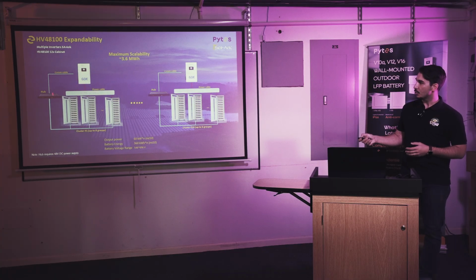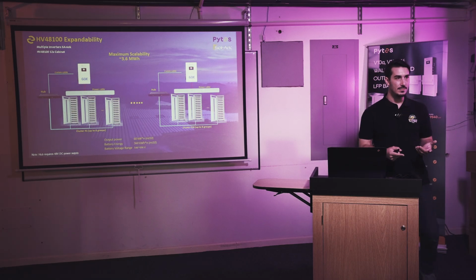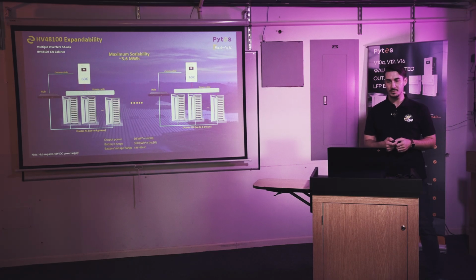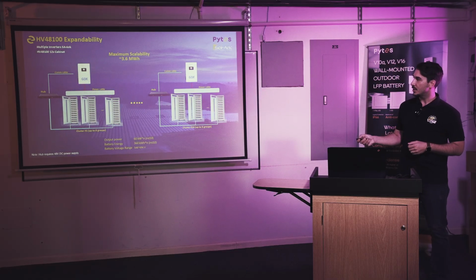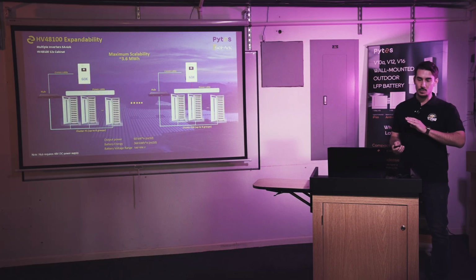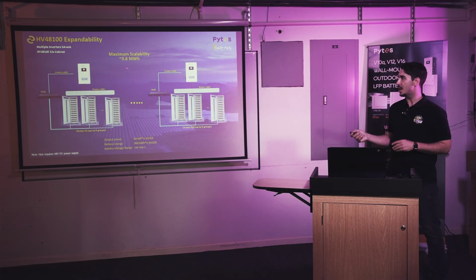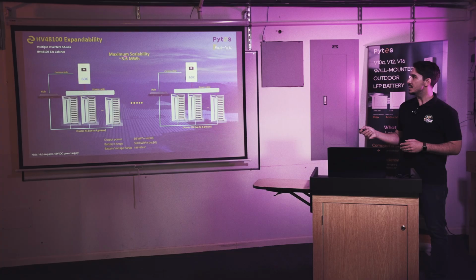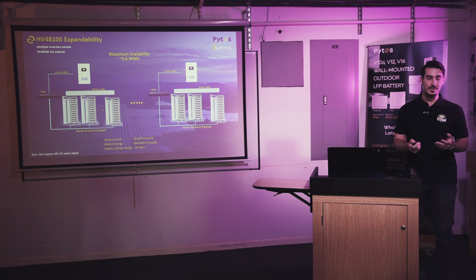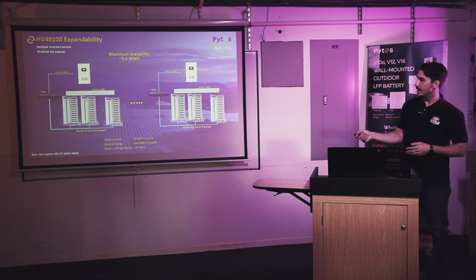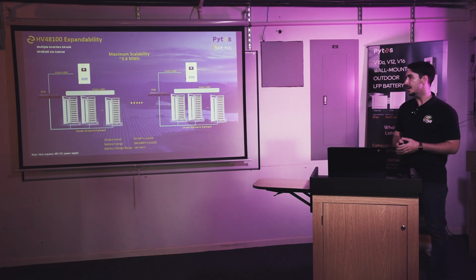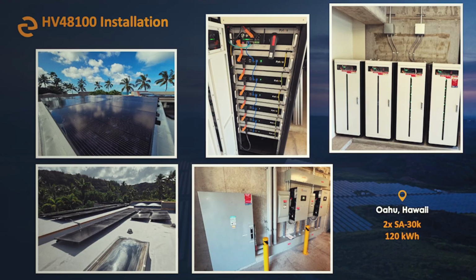You can look at this group over here and call it a cluster, if you will, and you can have up to 6 of these cabinets in one cluster on a single inverter. Now, Sol-Ark, you can do 10 60K inverters in parallel in a single system. So imagine this cluster duplicated times 10 inverters, right? The scalability on the high voltage side is way, way higher than anything low voltage we do. Low voltage, we top out at like 0.5 megawatt hour. High voltage, we can easily go close to 4 megawatt hours and even more in some cases. Because again, you can have 6 60 kilowatt hour cabinets, so 360 kilowatt hours per inverter times 10. And that's how you achieve these larger ESS products.